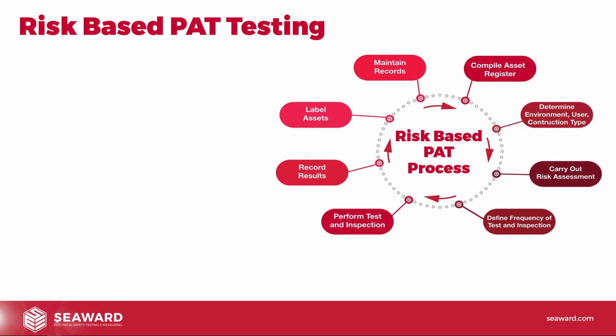So what we're advocating here really is a modern risk-based approach to PAT testing. Previously, PAT testing might have just been done on a regular basis. We just do it every 12 months. Nobody knows why. We just do it every 12 months because everything just gets done every 12 months. That's quite an old-fashioned approach. And generally, as I've probably said before, the 12-month time frame is not brilliant because it's probably too long for high-risk items and not long enough for low-risk items. So it's this halfway house that doesn't really meet any criteria.